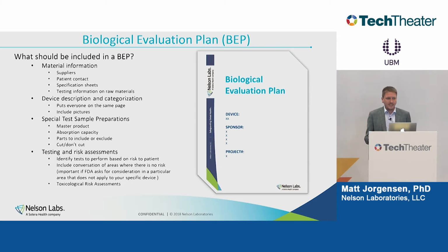You really don't want any surprises at the tail end of your submission, because this biocompatibility testing comes at the very end of the whole product development cycle. If you're going to do something like, say you have a titanium implant that's an ASTM grade, tested a million times before, and you want to say, okay FDA, we're going to demonstrate that this implant is very clean, and prove it's the same grade of titanium as other devices on the market, and for us that's good enough to evaluate biocompatibility — if you're going to try a strategy like that, the BEP is a great place to do that, because the FDA can take a look at it upfront and give you some buy-in, and maybe they'll say yes.